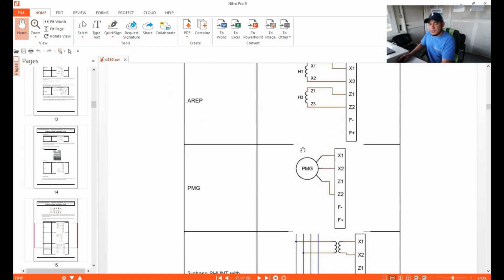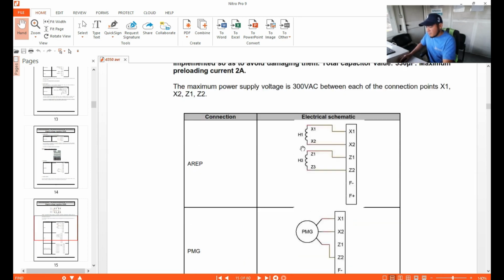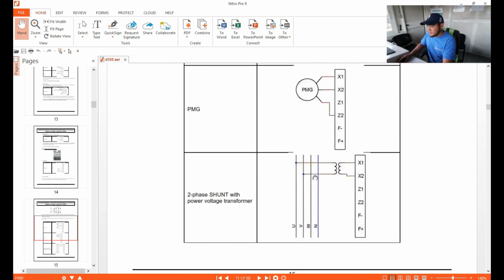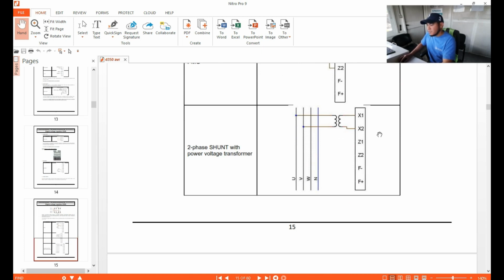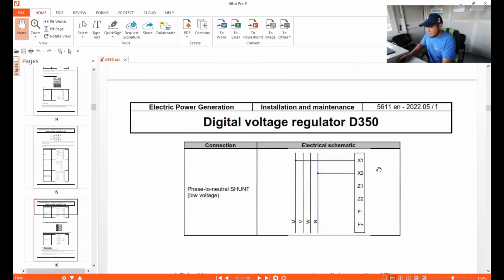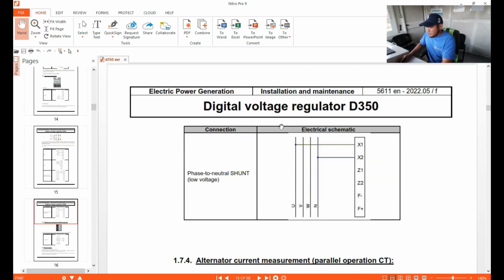Okay, so the rest of the other PMGs only output around 110 to 120 volts. But in the LEROY SOMER, in this type of AVR, it can be applied up to 300 VAC. So from the shunt connections, you can use it as X1 and X2. And this one is the single-phase connection. Okay, so UV, line to line. Okay, phase to neutral also, you can use it here in the shunt connections also. X1 and X2, no problem.